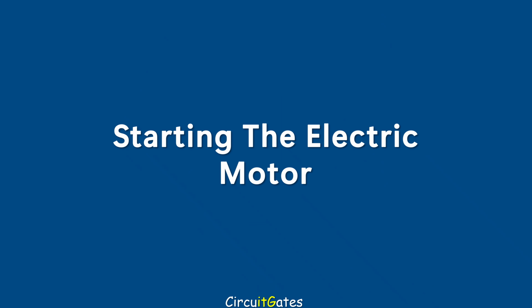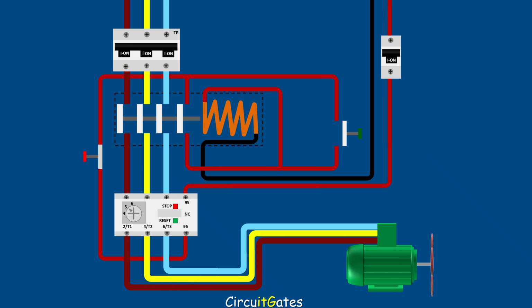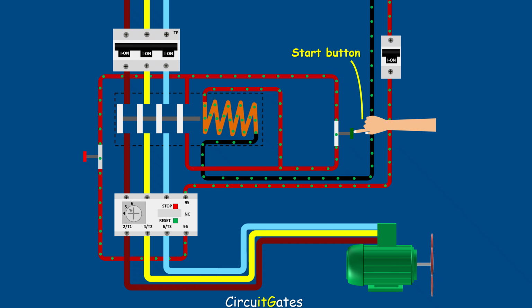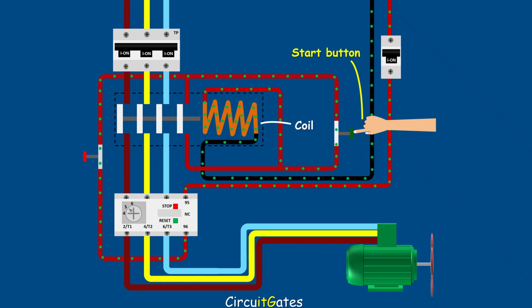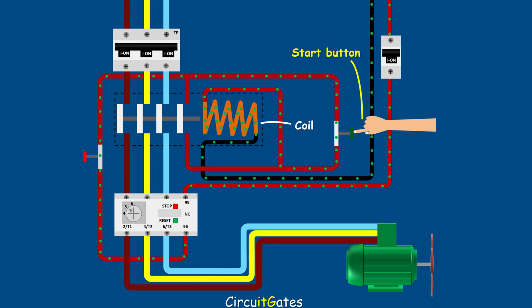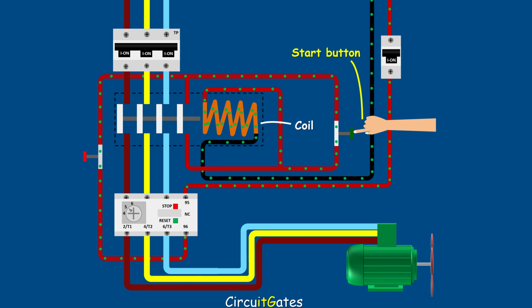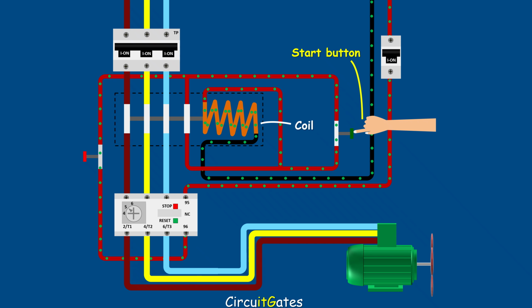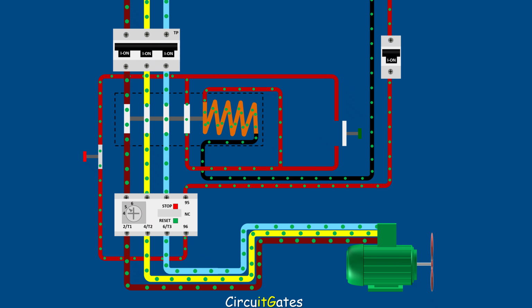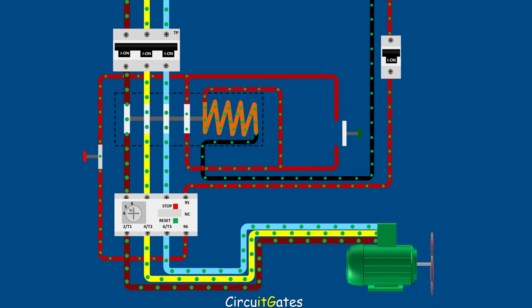Let us look at how a direct online starter works and how each component operates. When a direct online starter is correctly installed, to start the electric motor, the start button is pressed. This closes the control circuit, allowing current to flow through the contactor coil. When current flows through it, the contactor coil is energized and pulls the open contacts of the contactor to close, causing power to reach the electric motor, and the electric motor begins to run.